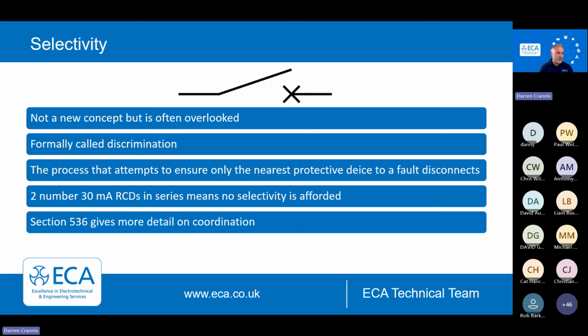There are additional protection. And the whole thing is actually that if we get a fault right at the end of our circuit, the device closest to that fault will disconnect. Certainly if we're following that 3-to-1 ratio, that will normally happen. There are times where sometimes you can't get away with 30 milliamp RCDs in series. And again, I go back to EV charging on this, where you might have to protect that circuit going out to the EV charger because it's in a wall, and then the EV charger might have an RCD built into it. So you've got two in series.